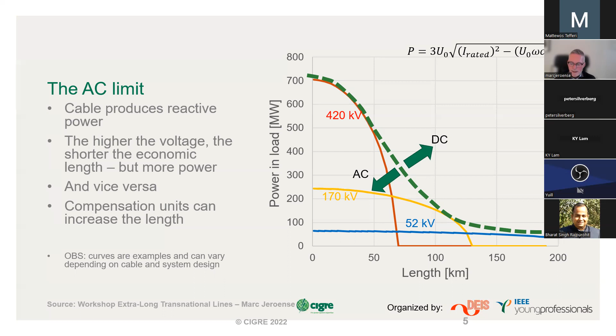The ohmic losses are still the basic ones left in your cable system, in the conductor. If you have a very long cable system—nowadays we're talking hundreds of kilometers—the losses increase. Then there's the old higher voltage technology rule: you go up in voltage, because for the same power, you can go down in current, and therefore have lower losses.